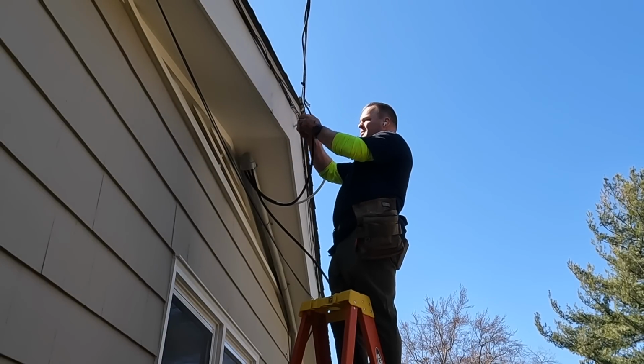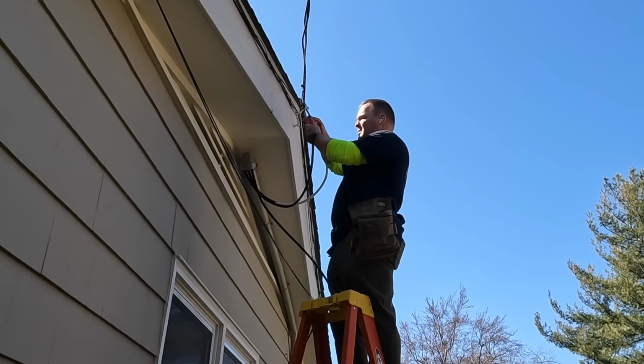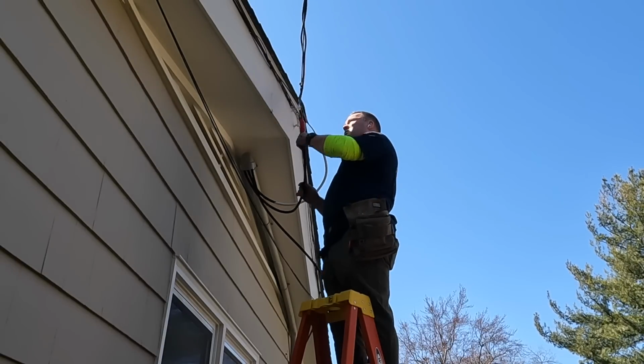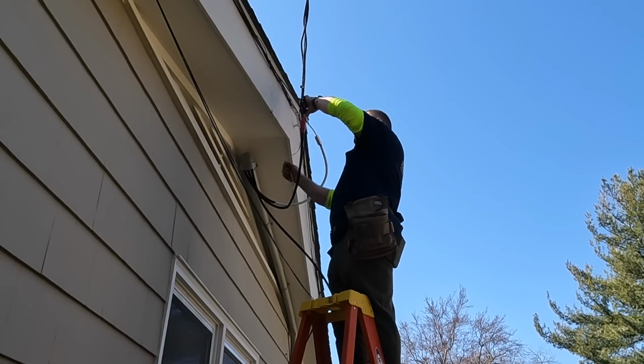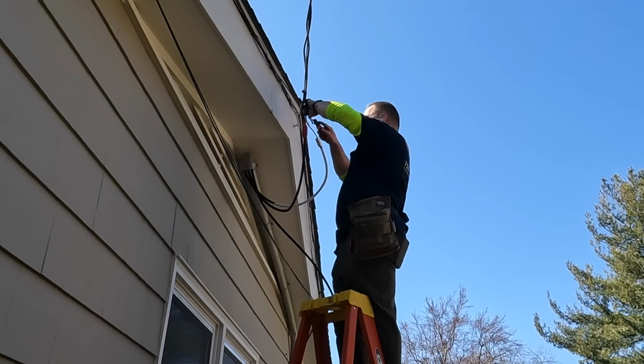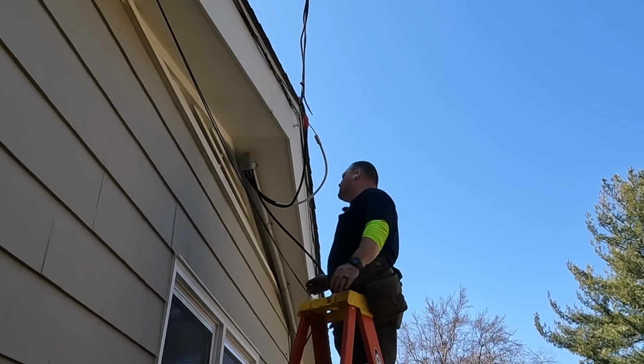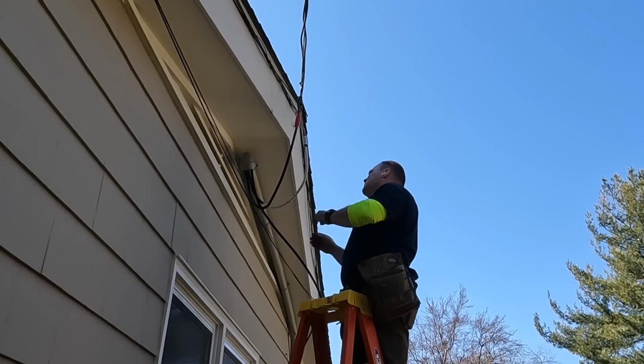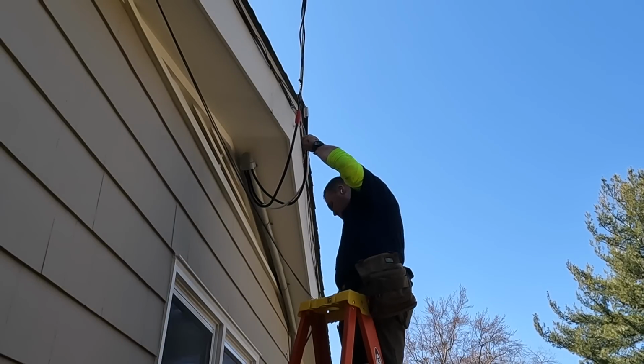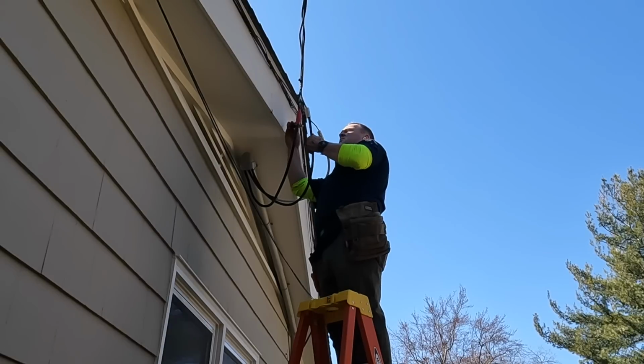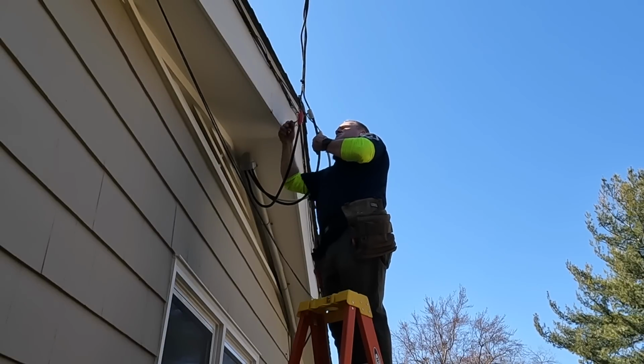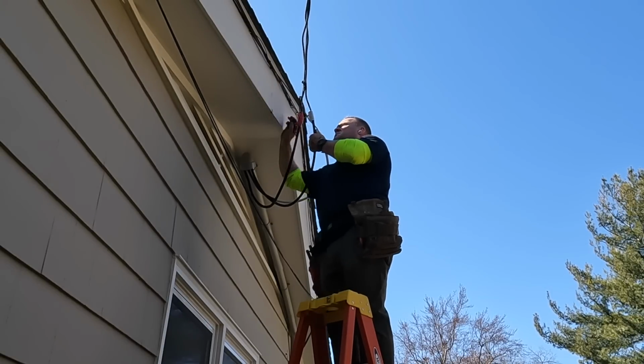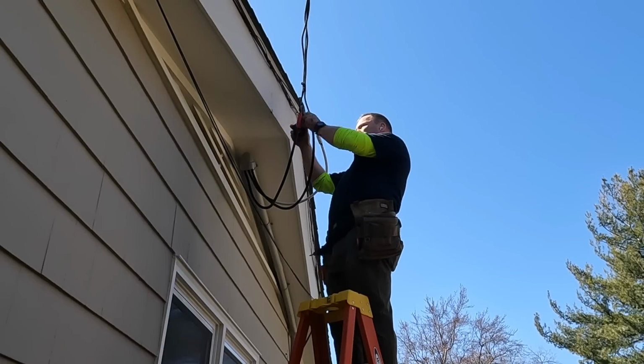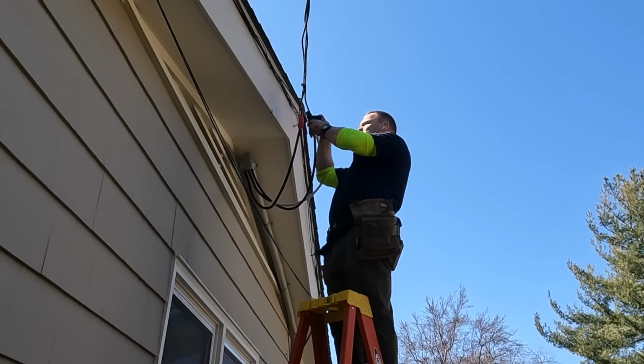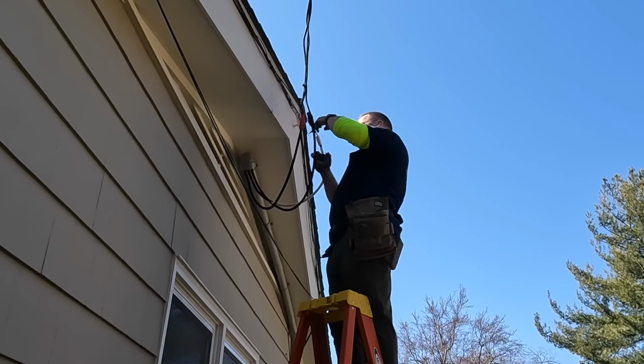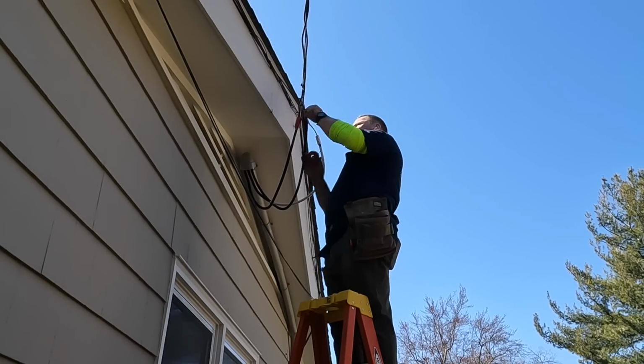The neutral conductor is obviously pretty important. If you lose that neutral conductor, your house no longer has any parallel connections, which provides a standard voltage of 120 volts to ground or to neutral. When you lose that neutral conductor, you'll have what's known as a series circuit, and everything in your house is connected in series. If you have multi-wire branch circuits, you could definitely jeopardize equipment attached to those circuits, just because of the laws of series circuits and parallel circuits.